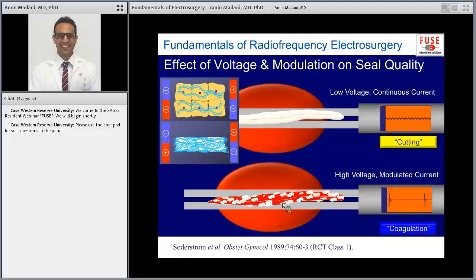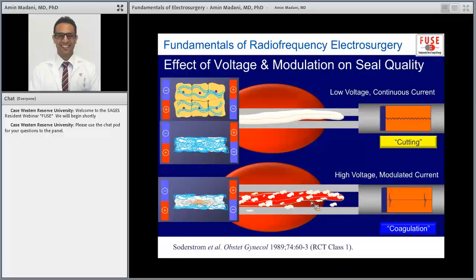The other thing is, remember when I mentioned you get caramelization when you raise the temperature so high? Well, that caramelization makes the tips very sticky. And so when you let go of your forceps, you actually release the seal. It can undo the seal, and you can get a suboptimal sealing effect. And what's actually important, if you notice the instruments that are like advanced bipolar sealing devices, like LigaSure and things like that, they're designed for hemostasis when you activate it. And they actually use a continuous low voltage waveform. So imagine that. You have a low voltage waveform designed for vessel sealing. So that tells you that this is the better way. So I hope I convinced everybody next time.